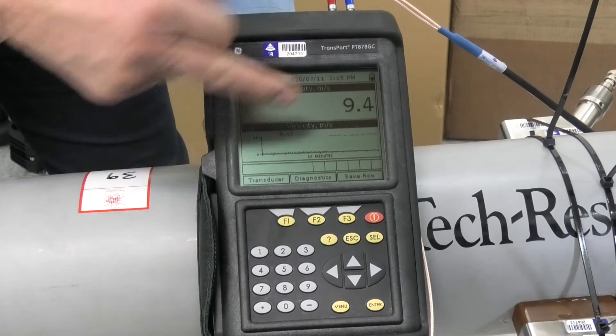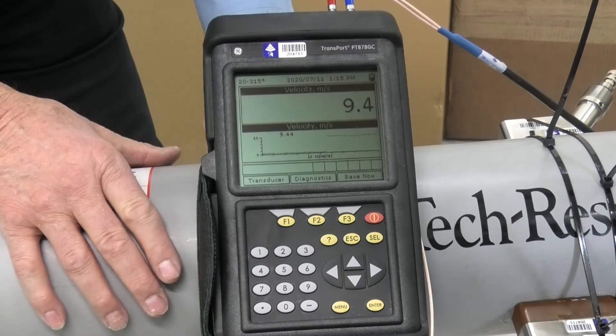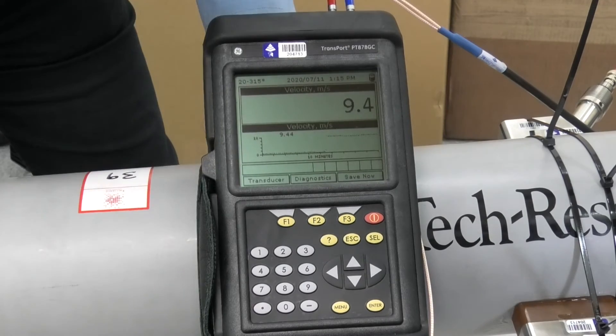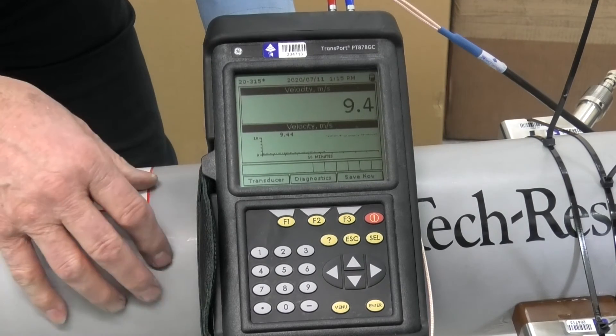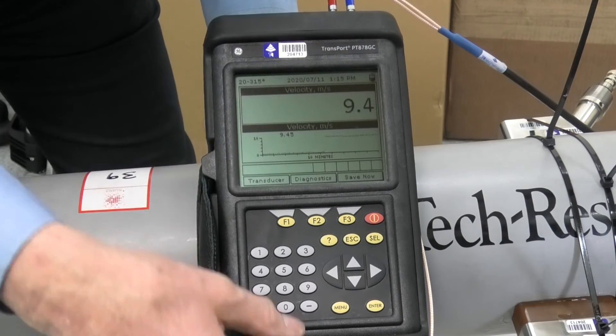Okay, we've turned the rig on, we're now making a flow measurement. The standard measurement on this rig, our default measurement is 9.4 metres per second, which this is showing at the moment. We use this for checking our airflow system. So that's pretty good.